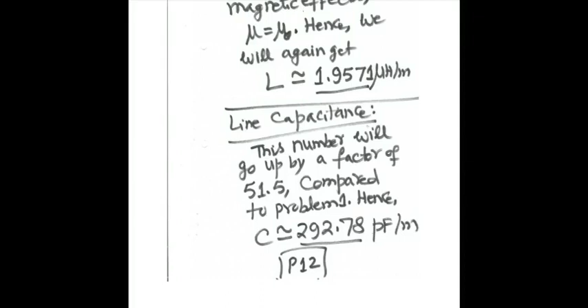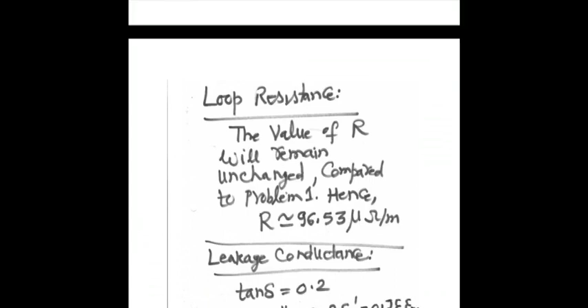Capacitance will definitely change. Instead of epsilon naught, you will be using epsilon naught epsilon r. So whatever value you got in problem 1 will now be multiplied by 51.5. Check it for yourself. So the result now will be 292.78 picofarad per meter. It is much higher than what we saw for overhead lines. Resistance will not change. It depends purely on the conductivity of aluminum. So that number would remain unchanged.